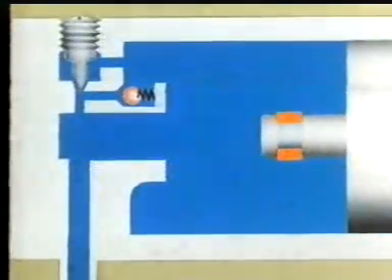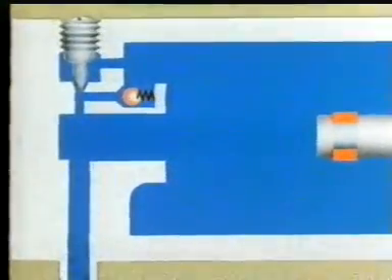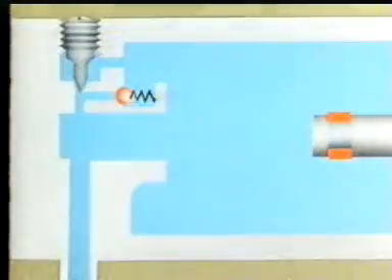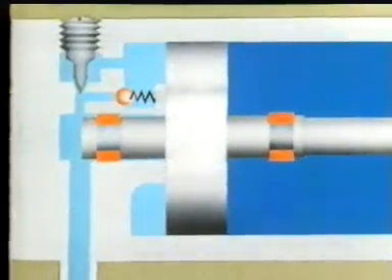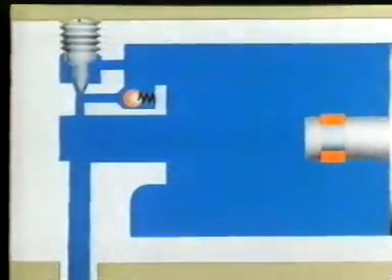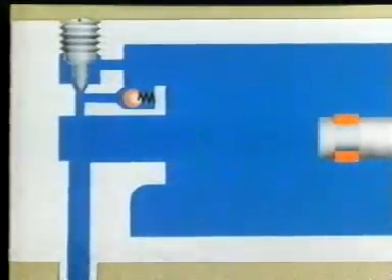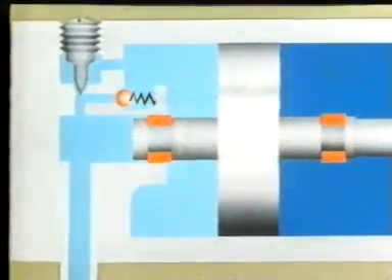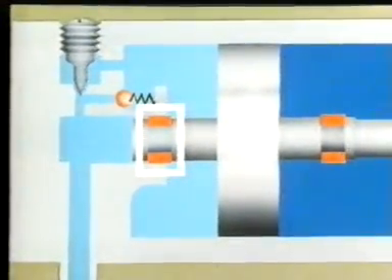If large masses are moved, an end position cushioning is used. It prevents hard impacts. The cushioning piston interrupts the direct escape path of the air to the outside before the piston has reached its end position.